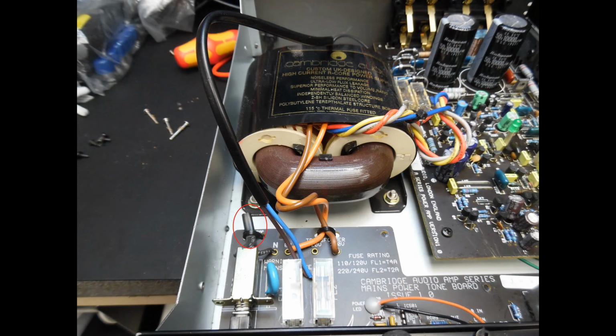One of the asks from the customer was to replace the power cable as it was showing signs of age and wear. So here what I've done is replaced it with a brand new cable - a 2-core with an integral moulded mains power plug. It's straightforward enough. You can see there's just some black cable ties securing it through the main circuit board, and then it solders directly near where you see the fuse carrier and the power switch.